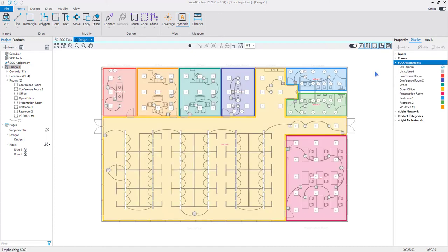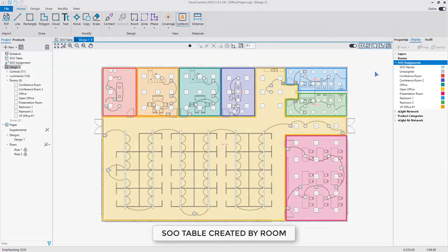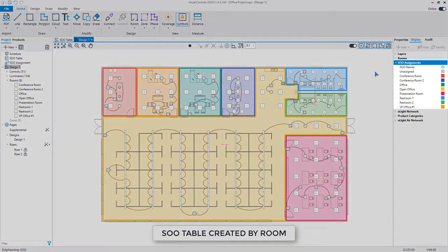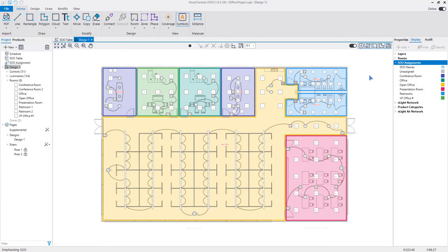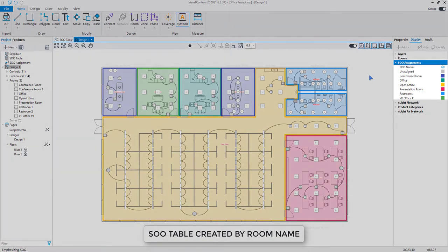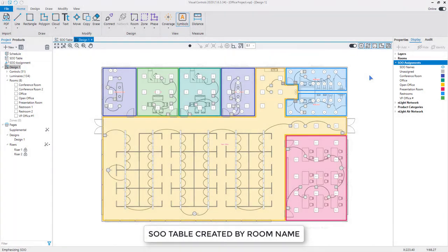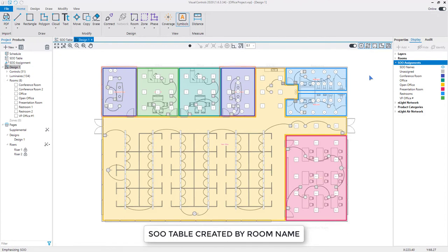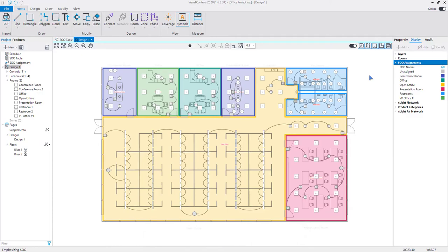Generating a sequence of operations table by room will assign a unique color to each room used in the design. SOO tables generated by name will assign unique colors for each name used for rooms in the design. If rooms share the same name, they will have the same color. This is one of the reasons it is important to be descriptive when naming rooms in the design.